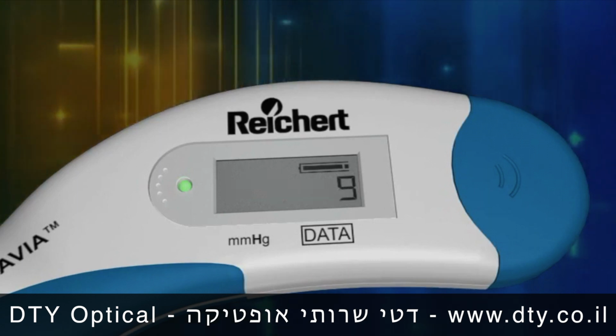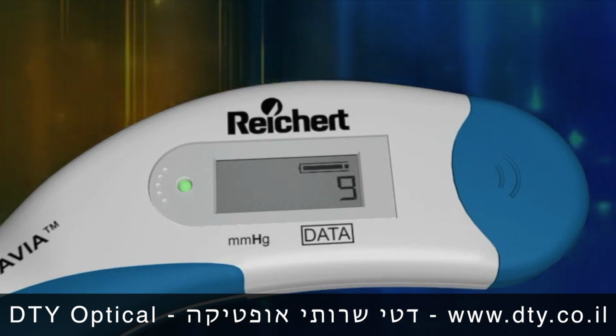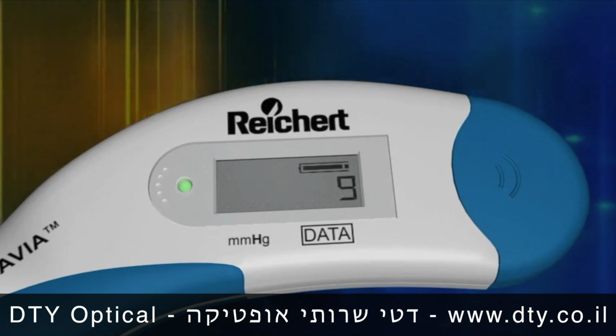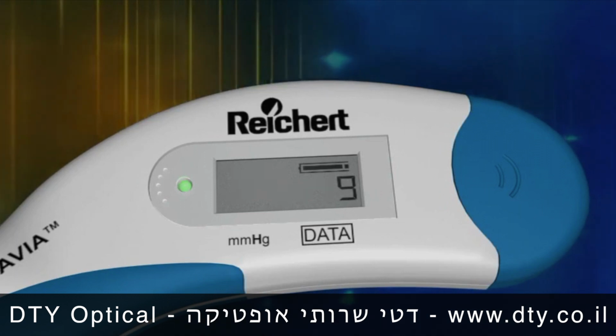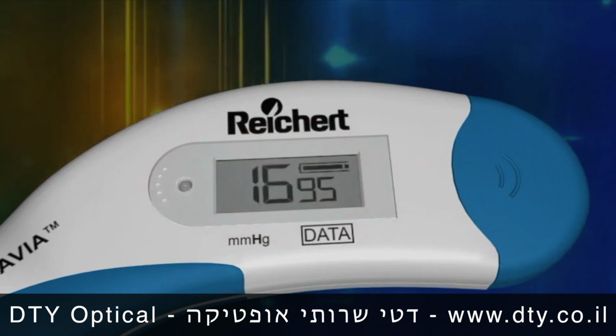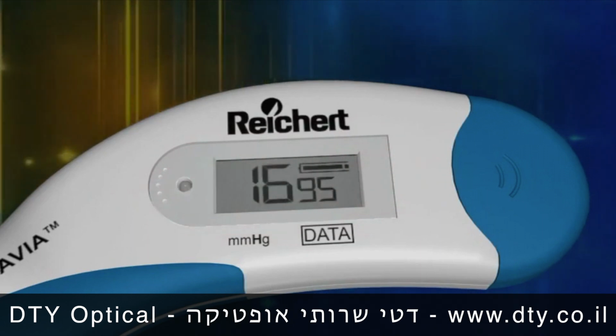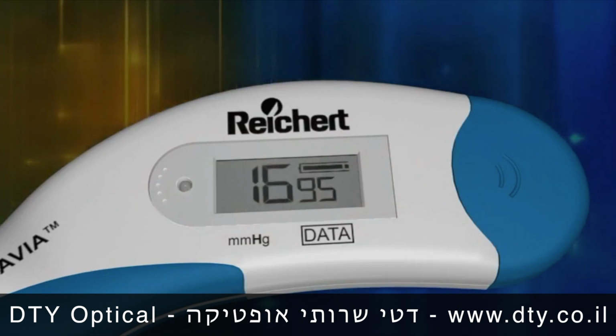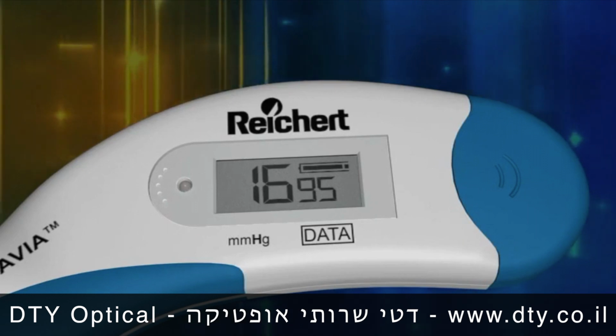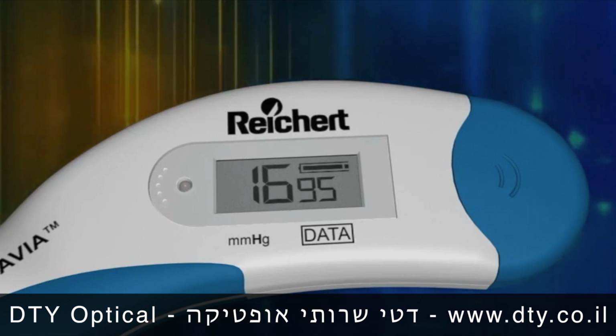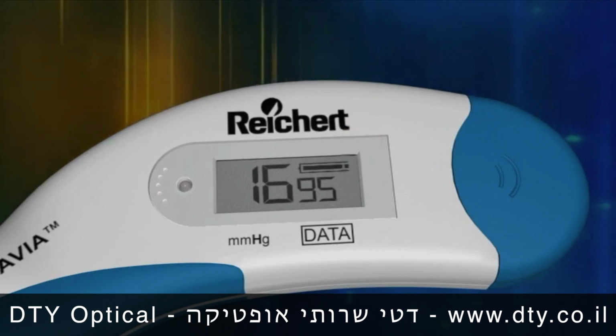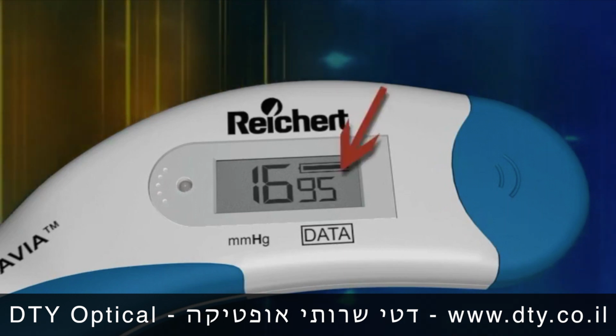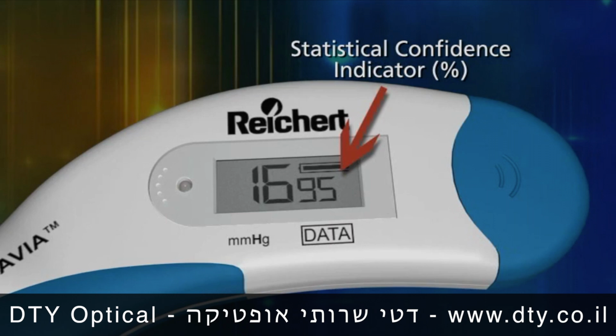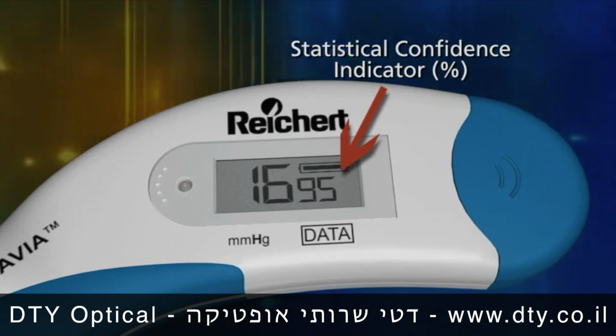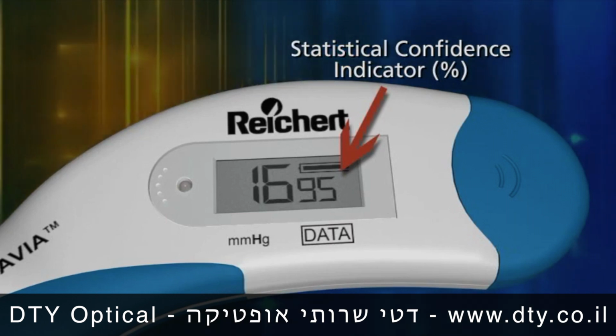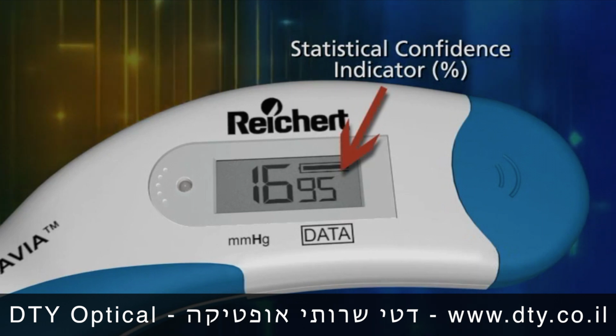After 10 readings are obtained, the device will beep and the LED will go out at the end of the measurement. The IOP reading is immediately displayed on the LCD. It's that easy. Notice the smaller 2-digit number to the right of the IOP measurement. That is the statistical confidence indicator expressed in percent. The higher the statistical confidence percentage, the more reliable the reading.